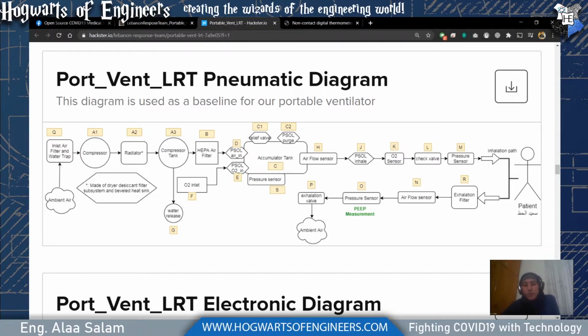Now, when we have control of air and control of oxygen, it specifies what percentage of oxygen we have inside something called an accumulator tank. The difference between the accumulator tank and the compressor tank is that the compressor tank has only air, at 21%, with no extra oxygen. The accumulator tank absorbs oxygen, and we control it with our control. We control something called the fraction of oxygen into the actual ventilator. We can raise the percentage of oxygen inside the air via the accumulator tank.